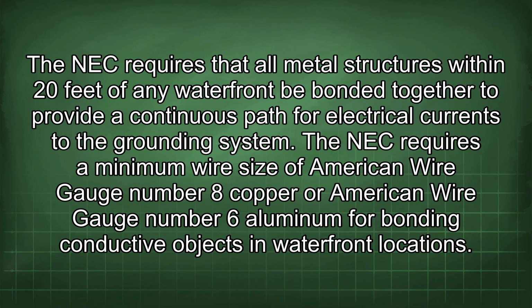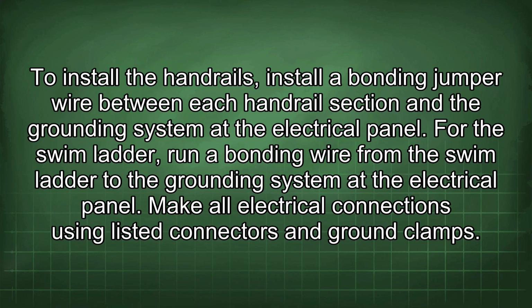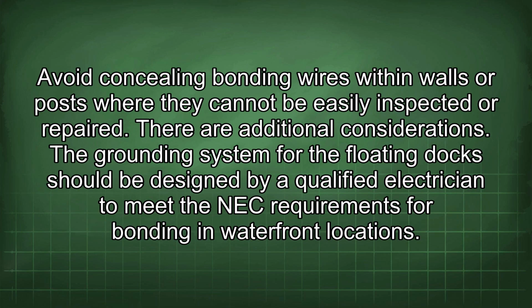The NEC requires a minimum wire size of American wire gauge number 8 copper or American wire gauge number 6 aluminum for bonding conductive objects in waterfront locations. To install the handrails, install a bonding jumper wire between each handrail section and the grounding system at the electrical panel. For the swim ladder, run a bonding wire from the swim ladder to the grounding system at the electrical panel. Make all electrical connections using listed connectors and ground clamps. Avoid concealing bonding wires within walls or posts where they cannot be easily inspected or repaired.